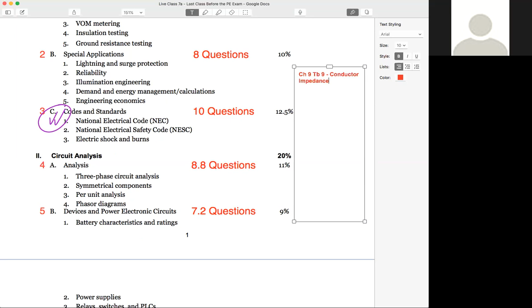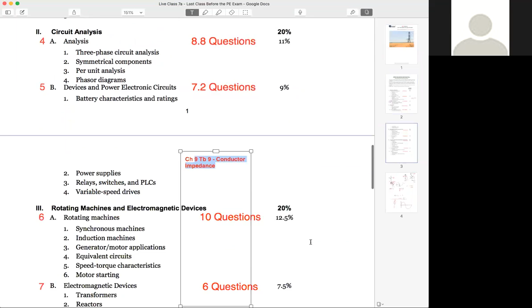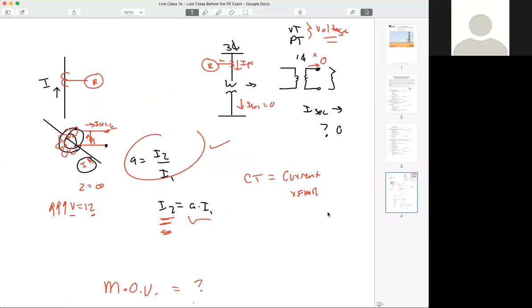Just off the top of my head for the NEC, I'd say be very familiar with Chapter 9, Table 9 - that's conductor impedance. Let's copy this down below... there we go, insert text. So just going off the top of my head, what I think is important - of course this isn't an exhaustive list - be really good with Chapter 9, Table 9, that's conductor impedance, your R and your X of L, or your Z effective.